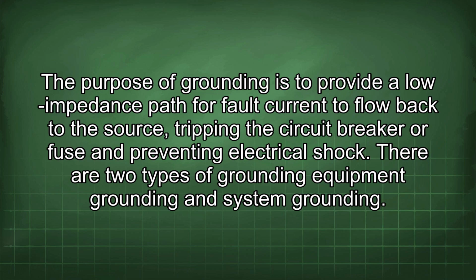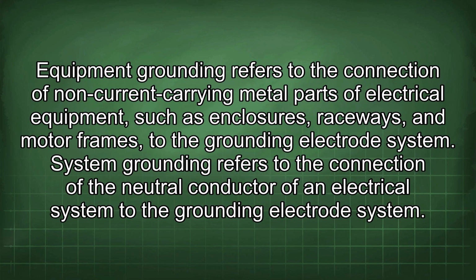There are two types of grounding: equipment grounding and system grounding. Equipment grounding refers to the connection of non-current carrying metal parts of electrical equipment, such as enclosures, raceways, and motor frames, to the grounding electrode system. System grounding refers to the connection of the neutral conductor of an electrical system to the grounding electrode system.